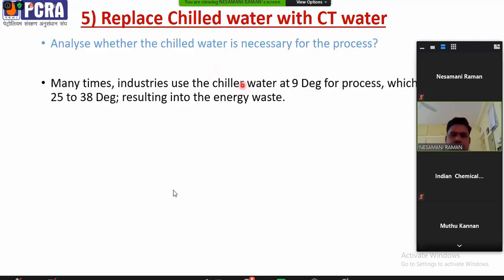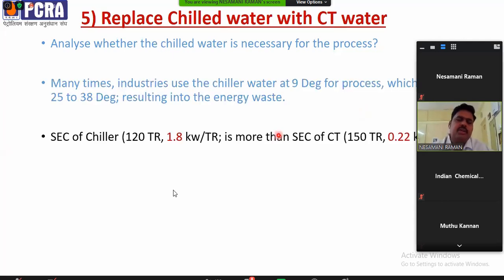So many times industries use chilled water at 9 degrees Celsius for a process which requires only 25 to 38 degrees Celsius, resulting in energy waste. Why are we worried about using chilled water? Because the specific energy consumption of a chiller is very high. For a 120 tonner, which we calculated during the audit, the chiller SEC is 1.8 kilowatt per ton, which is more than the SEC of a cooling tower, which is only 0.22 kilowatt per ton. Means for every ton, the chiller consumes almost 1.6 kilowatt more energy than the cooling tower.